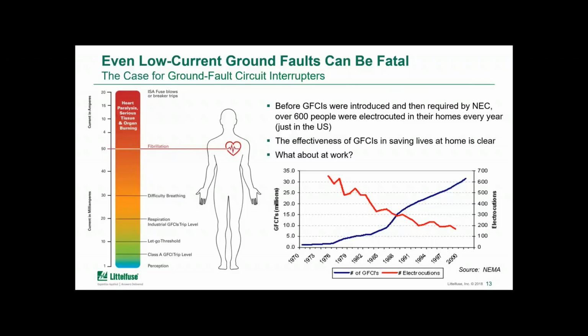And on the left, you can see the levels of current that we're dealing with here. So the first line drawn out on the graph is at 6 milliamps, which is the level of a Class A GFCI. And that is below the let go threshold. So that if there was to be a shock experience that is coming through a GFCI, it's below the let go threshold so that you're still able to let go.